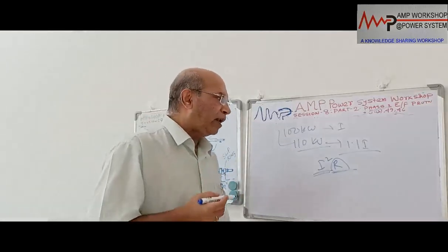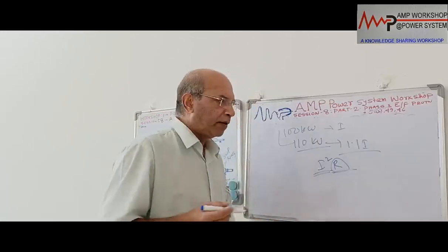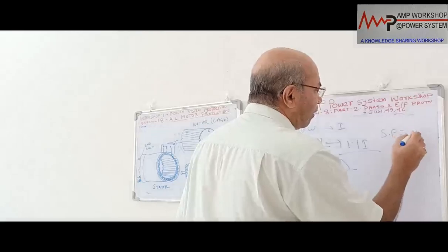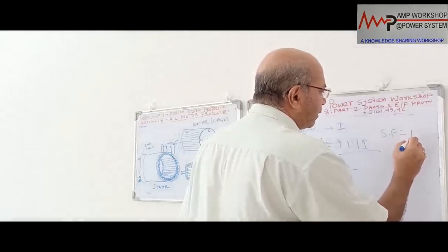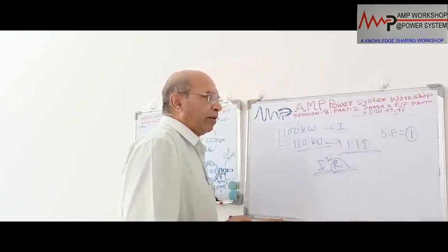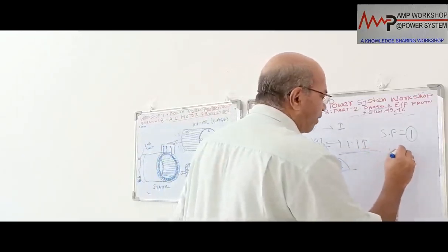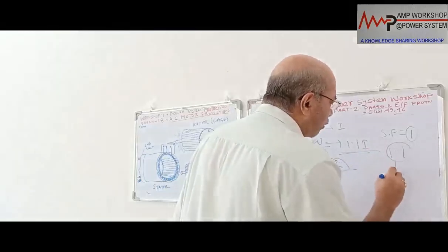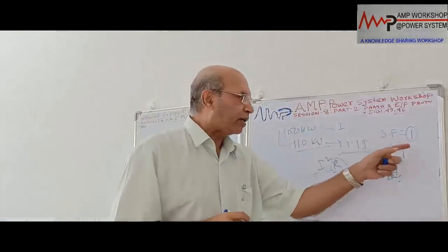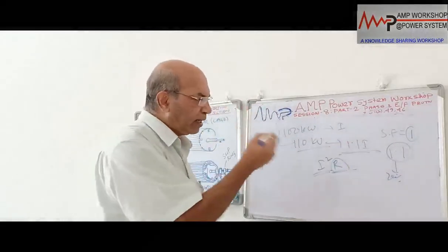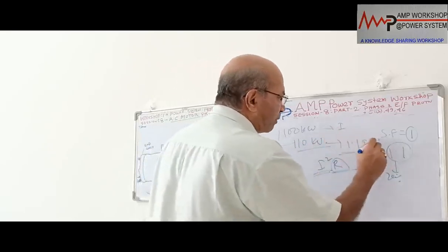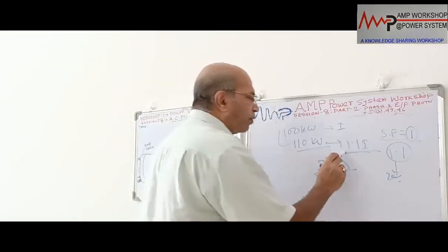And every motor has a service factor. In case of a service factor of 1, as per the NEMA motor guideline, we cannot overload the motor more than 10%. But if the motor service factor is, suppose, 1.1, in that case we can go up to 20% overload from the rating point. So depending on the motor service factor, there is a guideline in NEMA. Now we were considering, suppose service factor is 1, so we can overload the motor up to 10%.